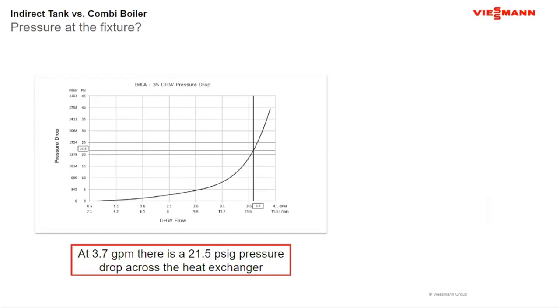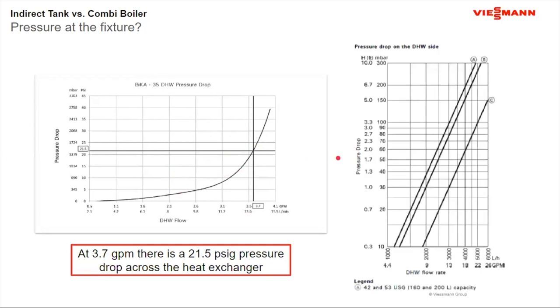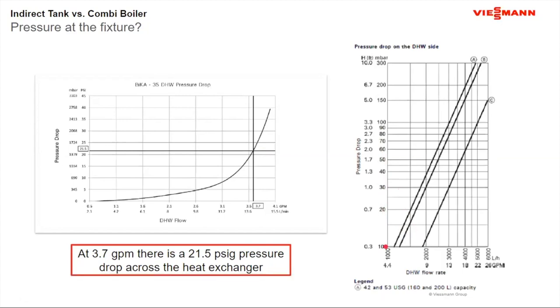And this is also one of the reasons why I like to see it with a bath or a bath and a half. I'm operating all the time down here, very low pressure drop across that heat exchanger. Conversely, if I do a tank style heat exchanger, you'll notice over here is my pressure drop, here's my flow rate. The minimum flow rate that even comes into consideration is 4.4 gallons per minute. So whether I'm doing one shower or two showers, the pressure drop across the tank is minimal, less than 3.3 feet. The performance at the shower from a pressure standpoint stays the same whether I have one shower, two showers, or two showers with a bathtub running. It gives me a much more consistent pressure with a tank style.